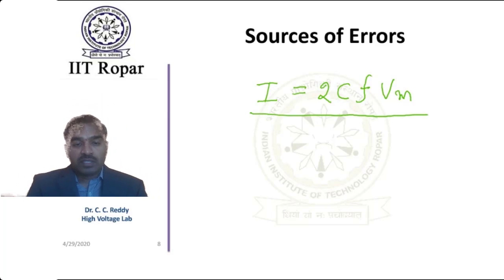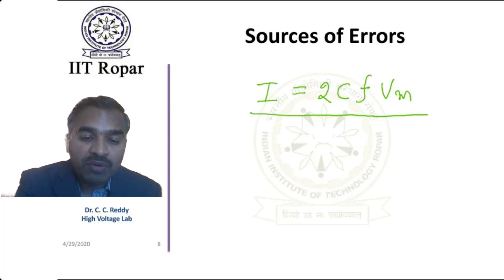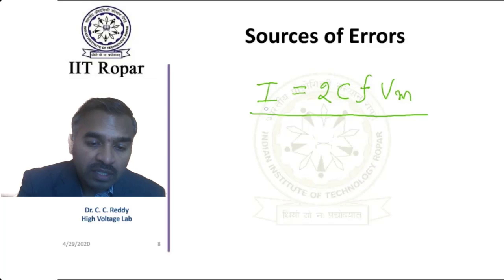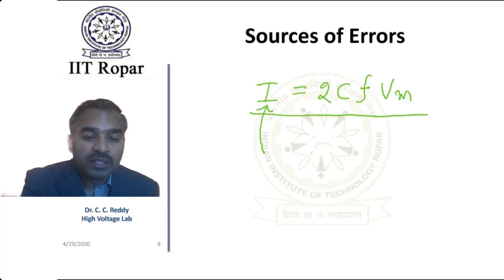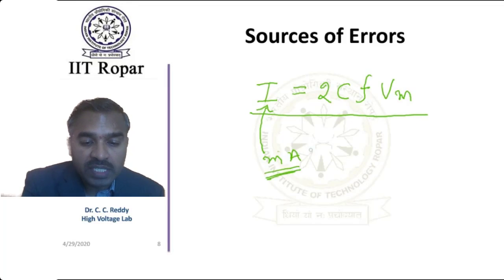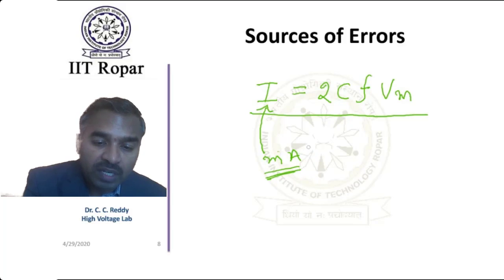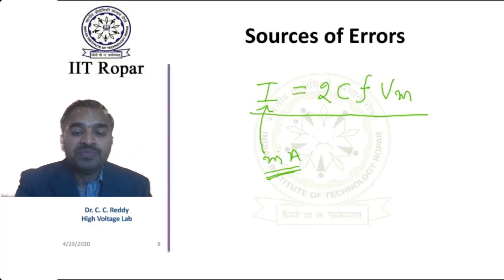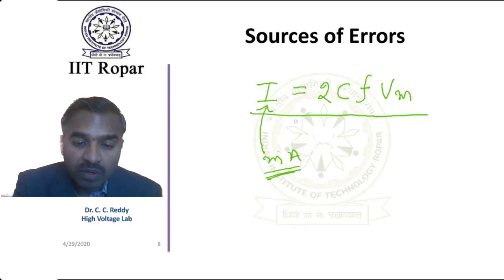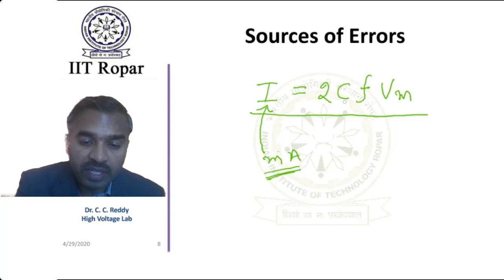Looking at this, you have to measure current accurately. The current is in milliamperes only, that range is in milliamperes, so it can be easily measured by a moving coil accurately. That is possible. Now, your capacitor should be having an accurate value.